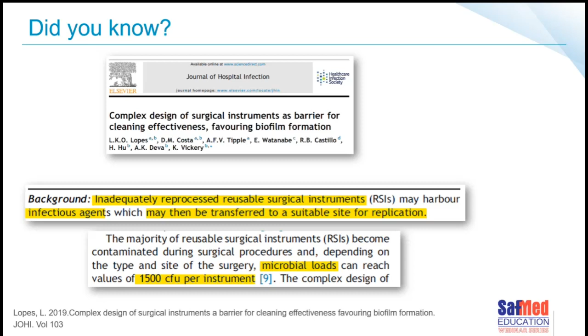But did you know that the microbial load on an instrument can be as high as 1,500 colony-forming units per instrument? That's incredibly high. So cleaning's job is to get rid of the bioburden as well as the potential microbial contamination before we even get to the next part of the process. Because if we try putting the instrument in the next process, which could be, of course, steam sterilization or a low temperature sterilization process, with this high volume of microbial load on it, there is no way that the steam or the sterilant is going to be able to kill all of that. It's just too much to expect.